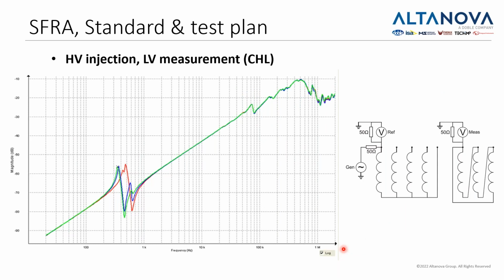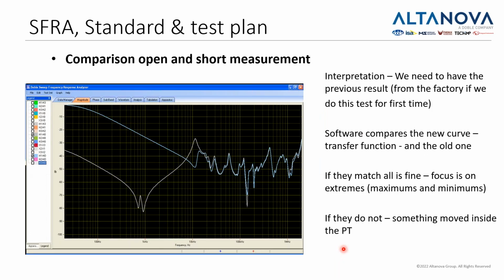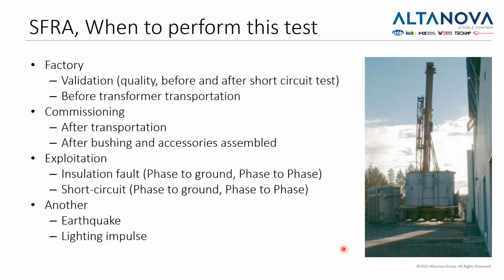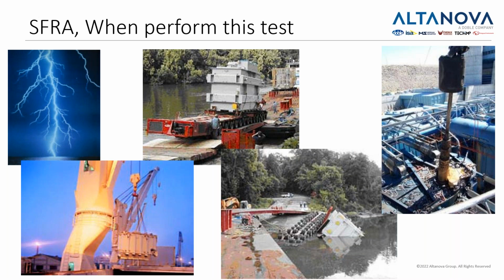So when we do all these tests, we compare, or actually we just load these results into the software, and the software does the comparison. What is important to say is that it is great if you have the result from the factory, because then you can compare with the original value. Now, we said that this test should be performed if we had some issues like the transformer fell into the river or there was a lightning hitting the transformer.